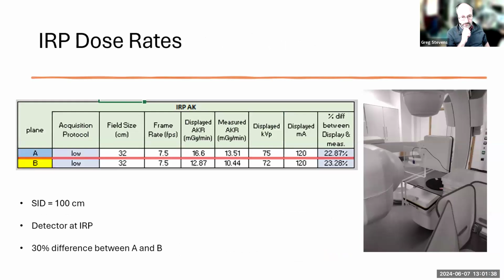That image just shows you how we measured the dose rates at the interventional reference point. This allows you to check the displayed dose rate against what we're measuring. It's just a single piece of PMMA with a dose meter attached to it. We're getting between a 20 and 30% difference between the two planes. We've only got biplanes, so those are the only systems I have any experience of.